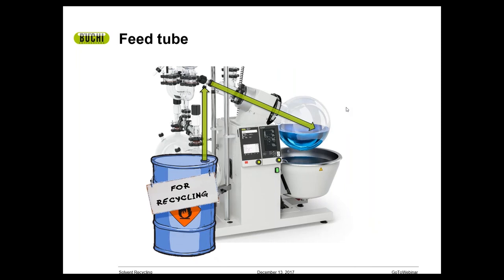Another benefit to using a rotary evaporator is the feeding tube method. You can have a tube connected to the inlet valve from your recycling bin. This allows you to introduce sample into the system without stopping the process — no need to stop the heating, rotation, or vacuum. Once the solvent gets low, you open up the inlet valve, the vacuum naturally sucks the solution into the system and fills the evaporation flask. When it reaches an adequate level, you close the inlet valve and the process starts all over again.